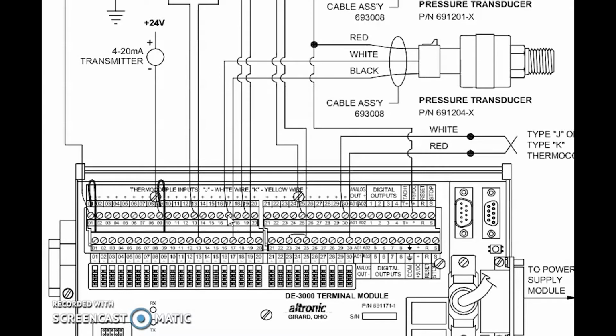So we want to always check the electrical connections to a pressure transducer before we start calibrating. The worst thing we can do is calibrate something to make up for a loose wiring connection. But if we've verified that we have a good 5 volt supply to our pressure transducer, and we've verified that we have a good ground to our pressure transducer, then it's safe to proceed with this procedure.